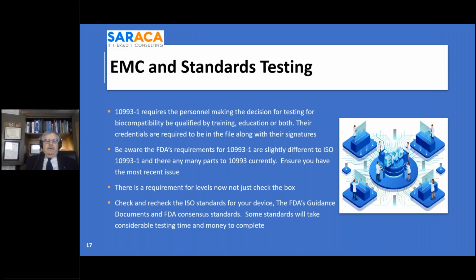Again, in 10993, there's a requirement for levels now, and if you exceed those levels, you have to explain why it's okay to exceed those testing levels, or find a way to get below them. They not only want to know what kind of plastic you have, but what's in the plastic, what kind of UV inhibitors, what kind of colors you have in there. And they want those levels known. You just can't check the box anymore.